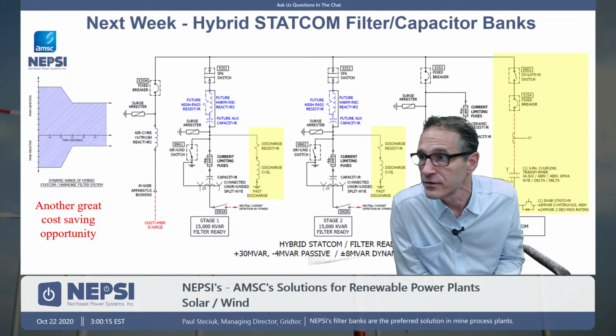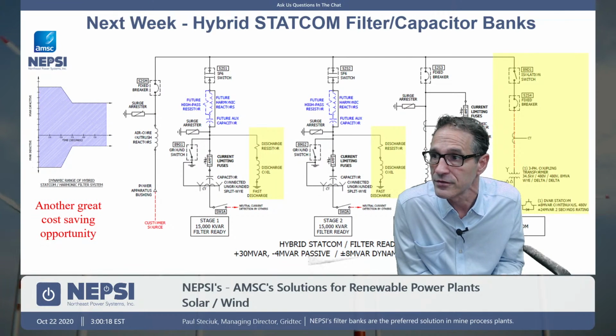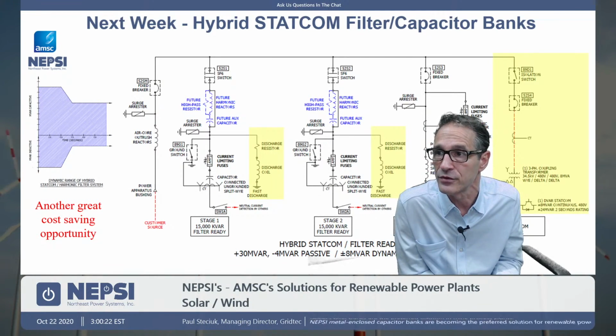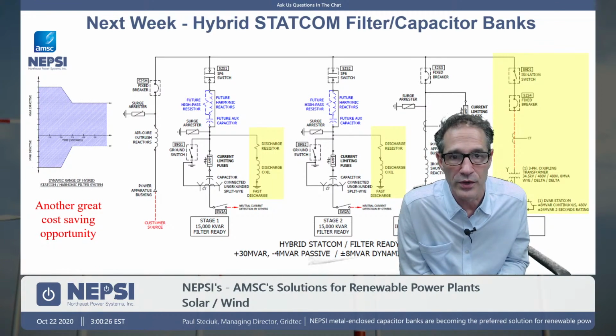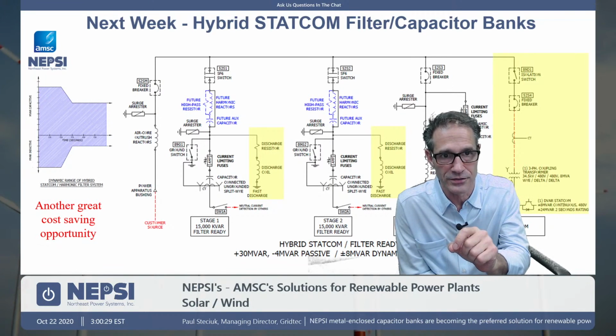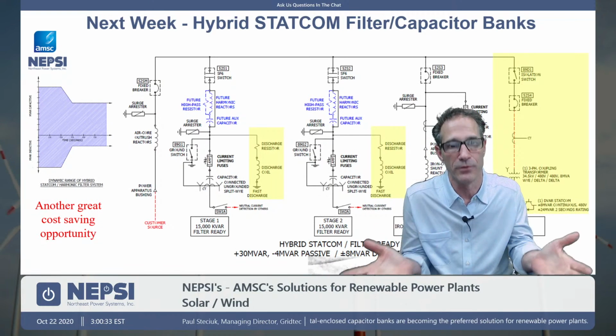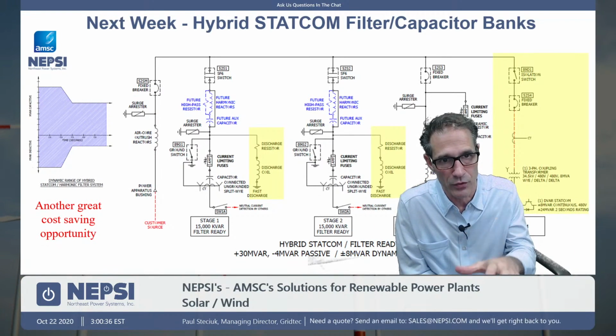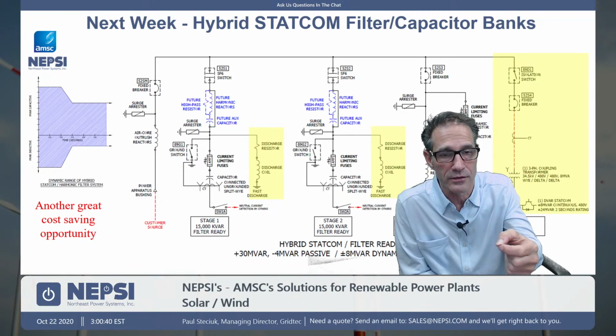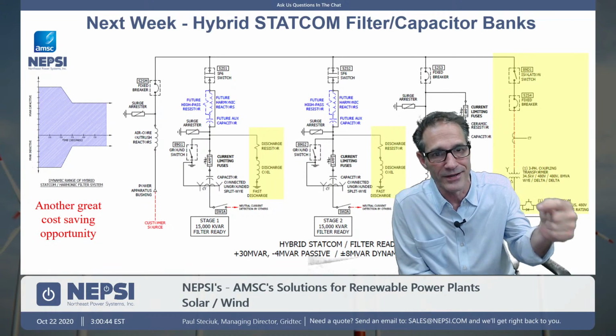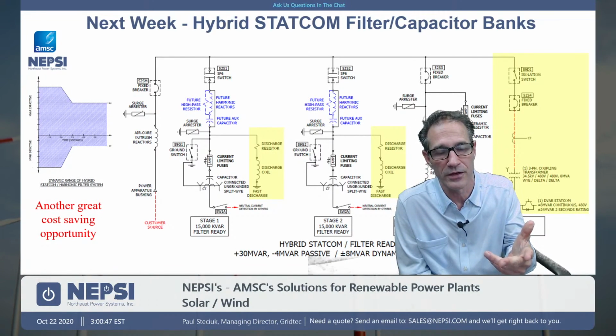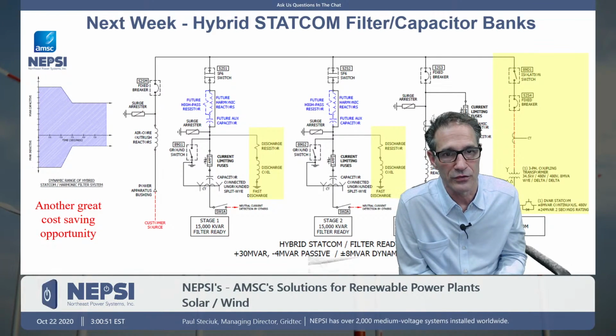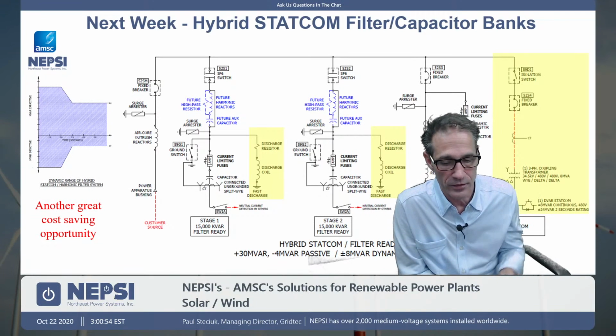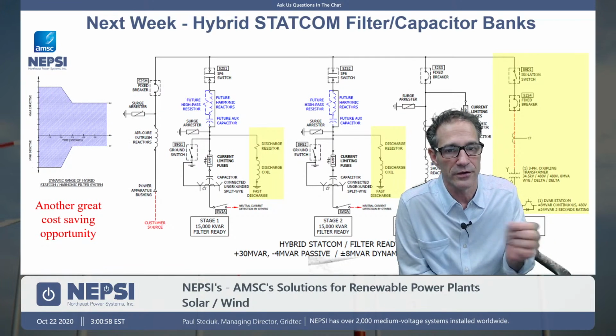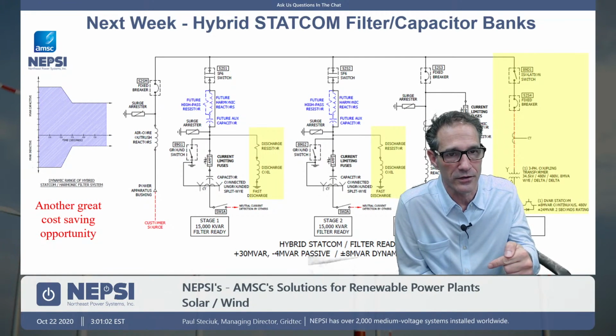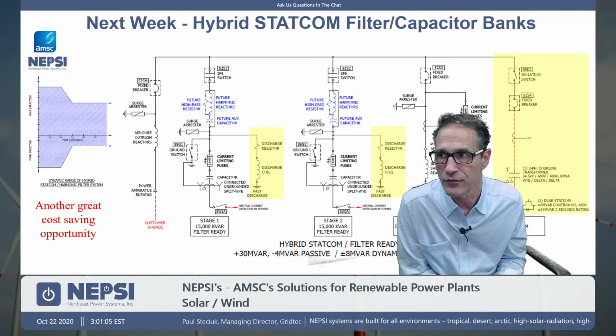Okay, so this is from Mansour. If everything else on the system is with 200 kV BIL, then should we not stick with 200 kV BIL for the switches as well? So that's a good question. A lot of the other gear in the substation will be rated 200 kV BIL because it's exposed to the environment. But if it's a metal enclosed solution, if you have roof bushings coming in, we would rate those roof bushings 200 kV BIL. But inside the gear, we would go with 150. And it's really about exposure. So very often outdoor gear is rated 200. Part of it's because of contamination of the bushings and potential for wildlife hitting the insulators. But once you get inside the gear, go with 150, and it leaves the choices open for us.